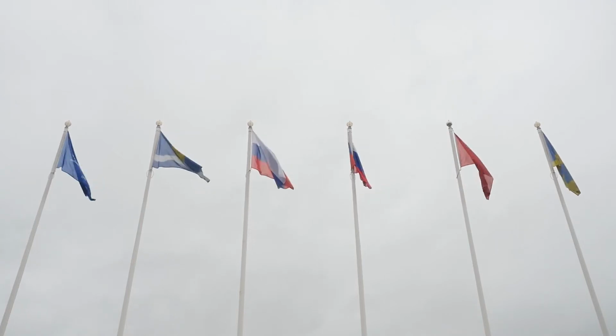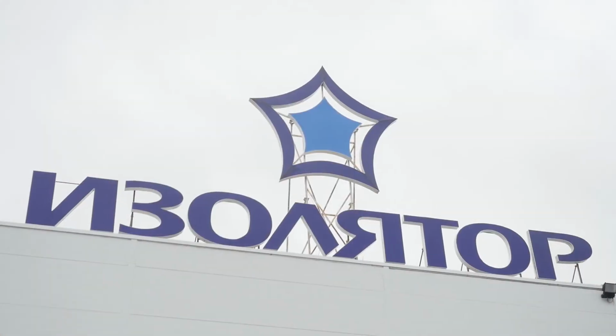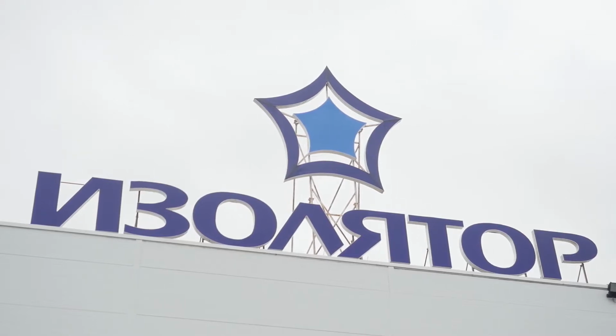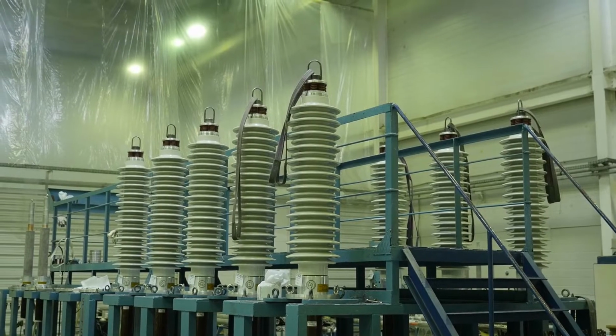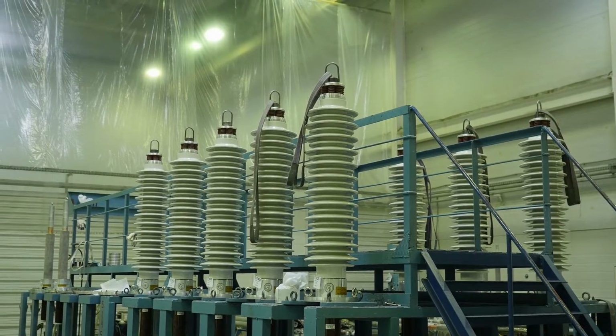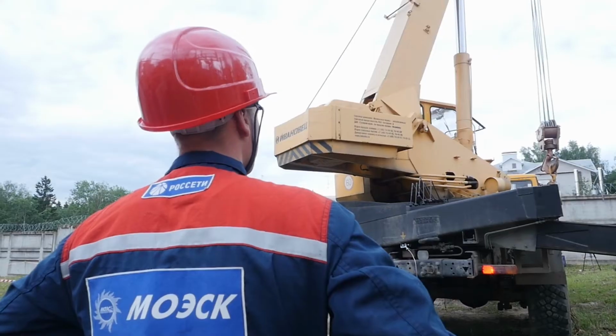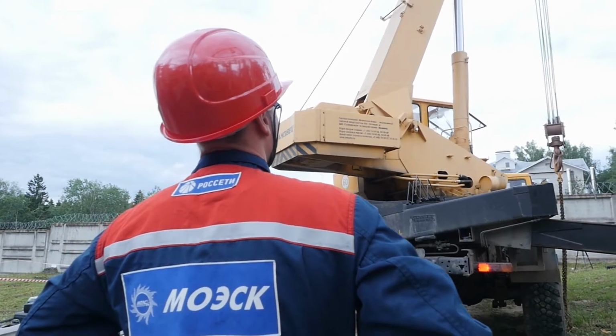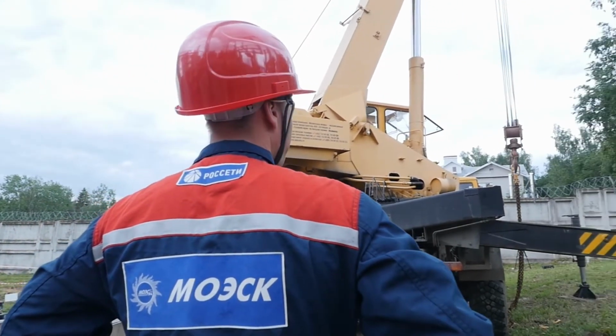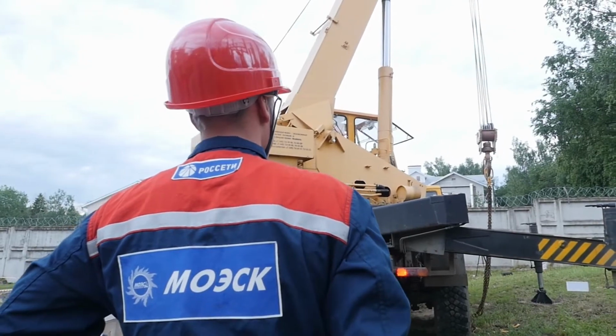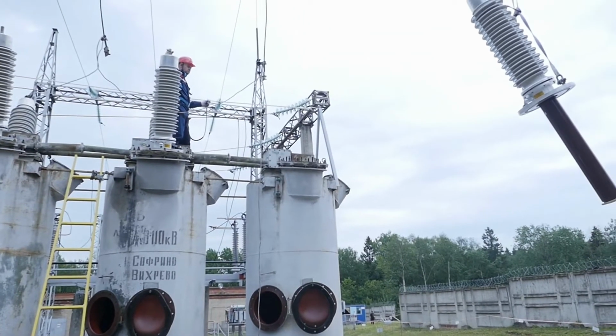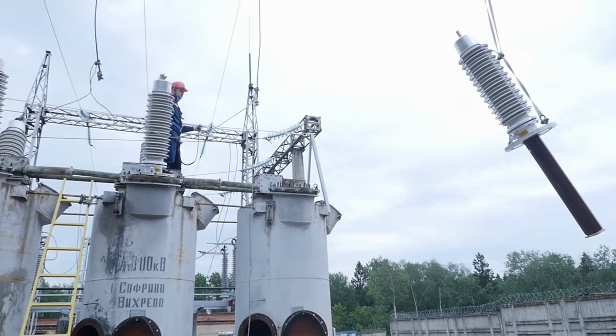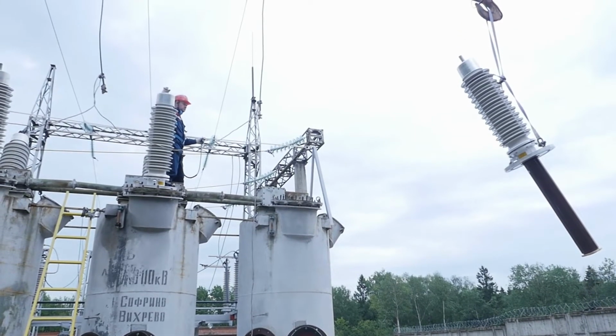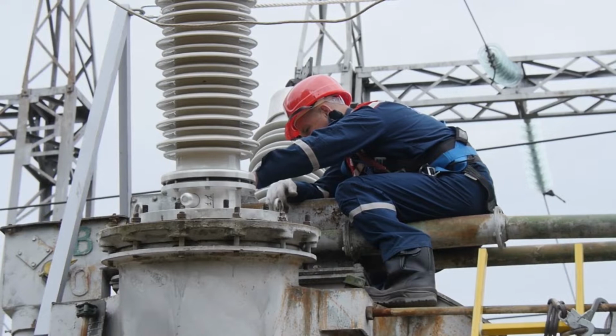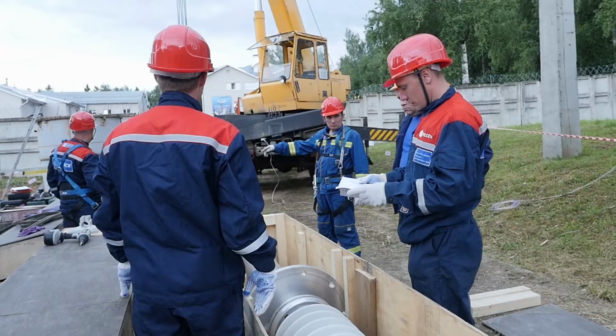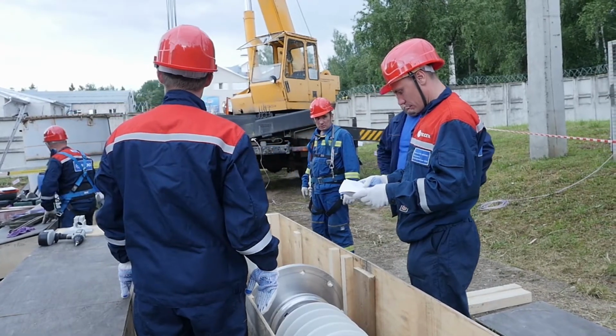Isolator has been successfully developing and producing RIP bushings of up to 800 kilovolts for over 15 years. Mass use of these bushings in Russia and in the power industry of other countries shows that bushing installation on equipment is an essential stage ensuring its successful operation. Due to design features of RIP bushings, this procedure differs significantly from equivalents with other internal insulation types and requires an accurate studying and strict observance of all manufacturers' instructions.